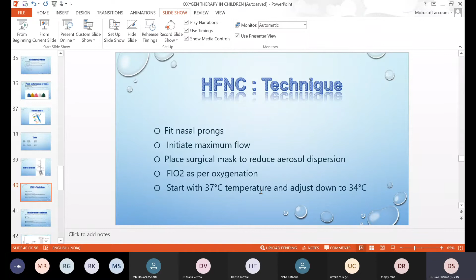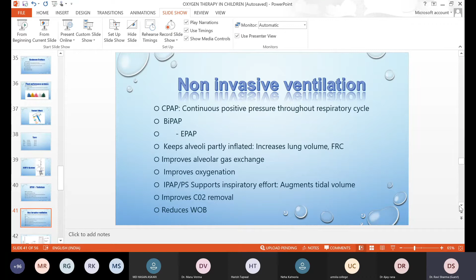Next is non-invasive ventilation. These are basically two CPAP devices here. I am going to show you the CPAP, that is, as the name implies, continuous positive airway pressure, and then the BiPAP, that is bi-level positive airway pressure. Here we are going to give two pressures to the patient. These are the pressure devices. The low flow devices we discussed till now worked on ambient pressure, but these are high pressure devices. Here we provide the gases to the patient at a pressure level, so that the gases can reach the patient's alveoli.